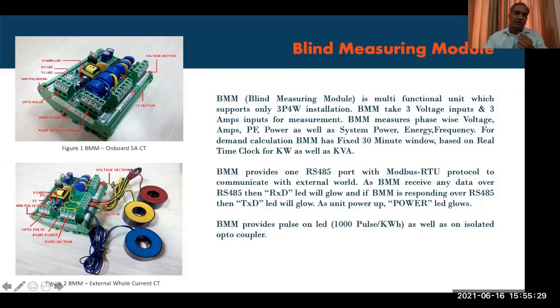This comes in two versions. One is a CT operated version, where you can put external CTs as per your load requirement. The other comes with an 80 ampere inbuilt CT, so when your machine load is low and you don't want a cumbersome external CT, you connect the load through this built-in CT and measurement starts happening. The CT is a class 0.2 accurate nylon CT, so everything measures accurately from here.